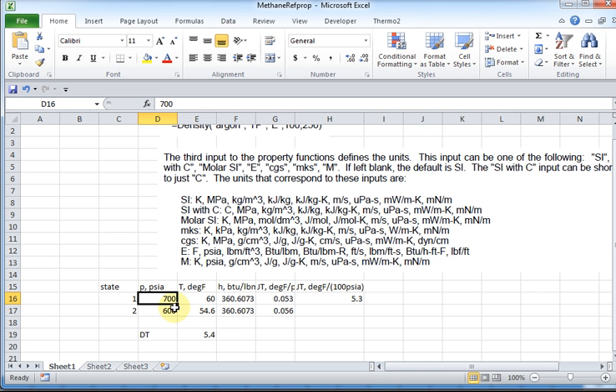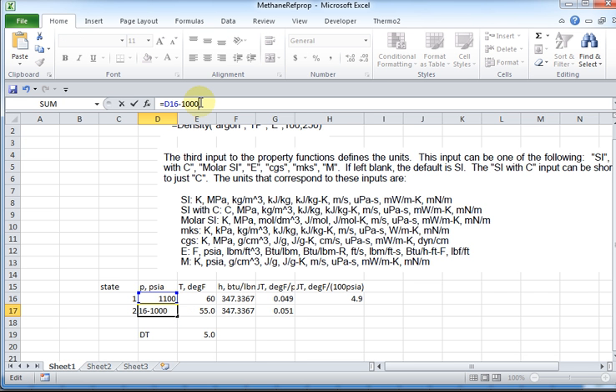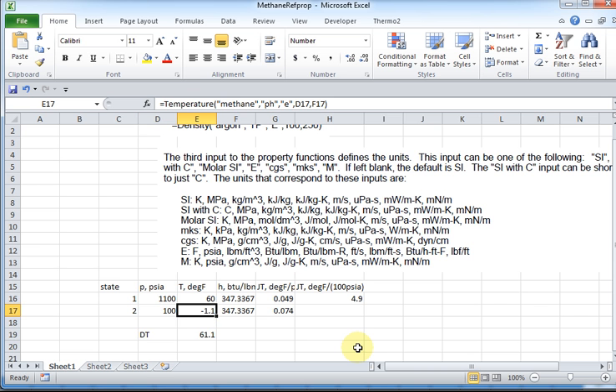Remember what would happen if we come in with 1100 PSI and drop it not by 100 but by 1000 — notice that temperature in degrees F is way below 32. If there's any water in the methane in the pipeline and you have a restriction or are closing a valve with a little flow still through it, what's going to build up on the other side is ice — water hydrates — and it'll continue to build up until it plugs the valve. When you want to go back and open it more, you won't get the flow rate through it. That's why the Joule-Thompson effect is discussed in natural gas and pipelines, and why when you push in a supply from a different well you need to get the water out — it's a bad actor.